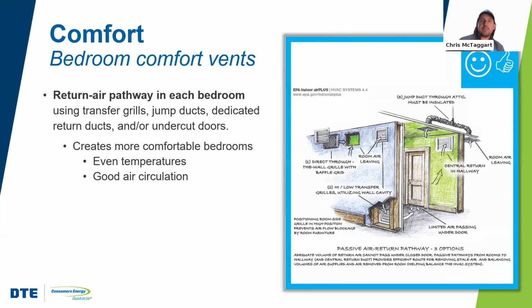Bedroom comfort vents - basically that's making sure we have balanced bedroom heat and cooling distribution. We do that usually through either dedicated returns, jumper ducts, or door undercuts.